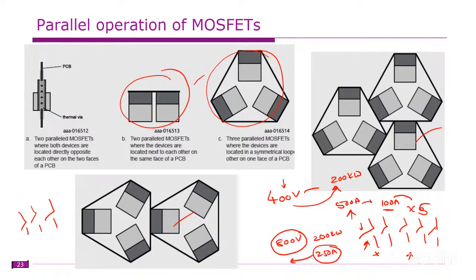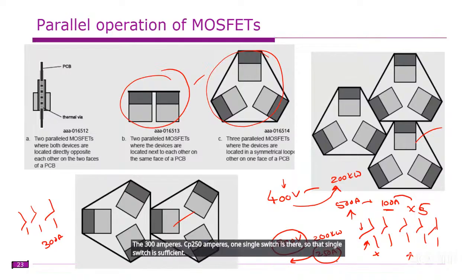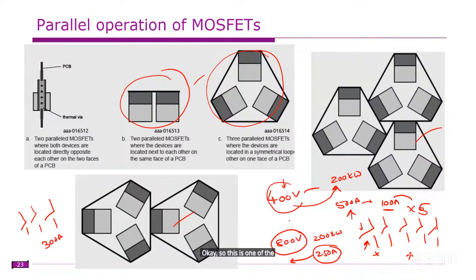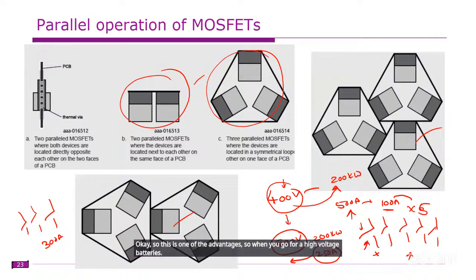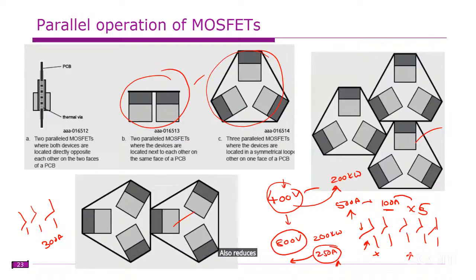If you choose only a 100 ampere switch, three of them can simply carry 300 amperes, or with a 250 ampere switch, a single switch is sufficient. This is one advantage of high voltage batteries: the current is reduced, I-square-R losses are reduced, and with higher voltage, power transfer capability is also more.